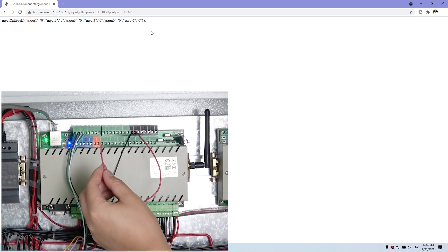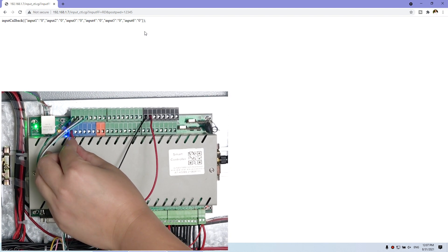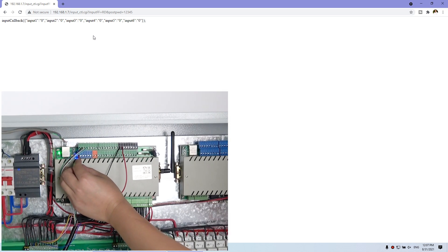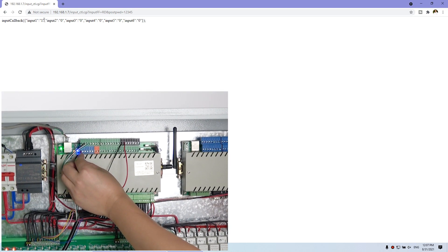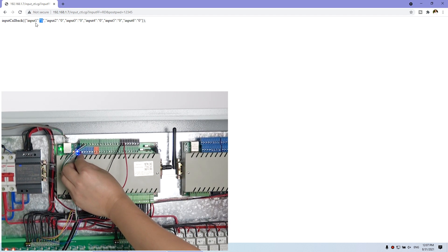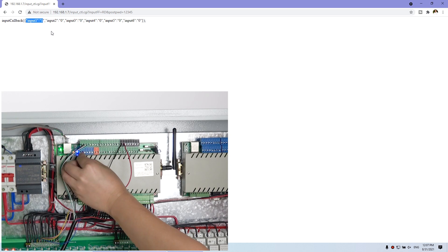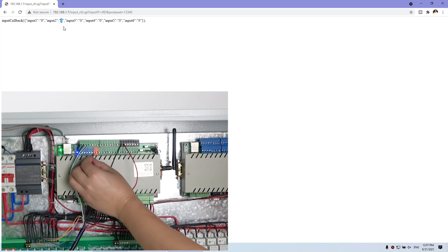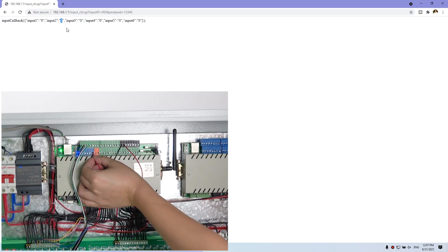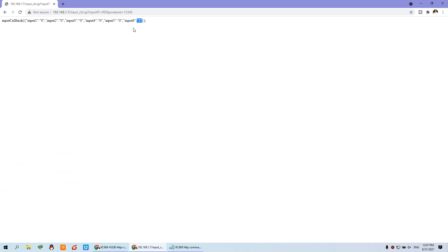If I use a wire to short — this is ground — I can trigger number one input. I short input one, and after I set the sensor mode from the last video, I refresh the web browser. You can see the input one changed to one — it is triggered. So I have shorted input one. If I short input two, you can see input two is triggered. I refresh again: now input one becomes zero and input two becomes one — it is triggered. Also, I can trigger input six — this is channel six. Refresh, and you can see channel six becomes one. So this is how to send the HTTP command by yourself.